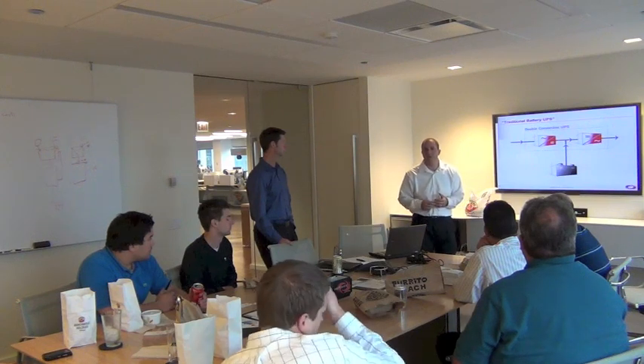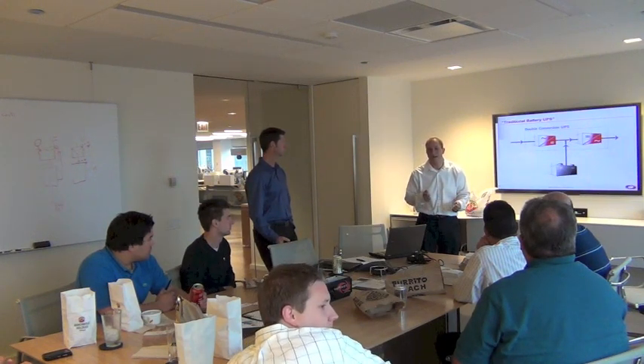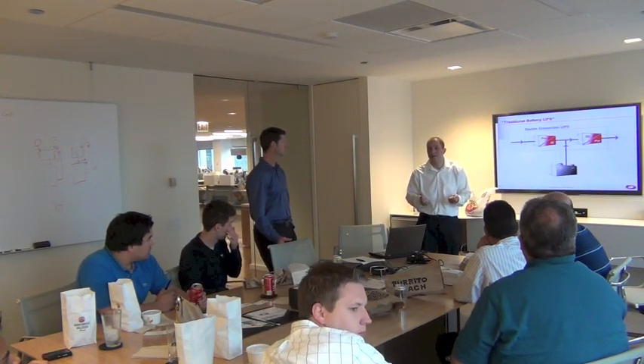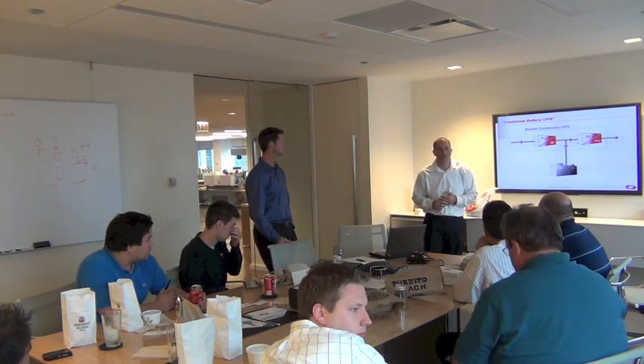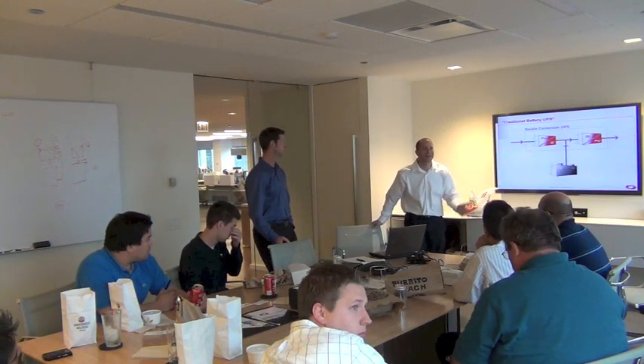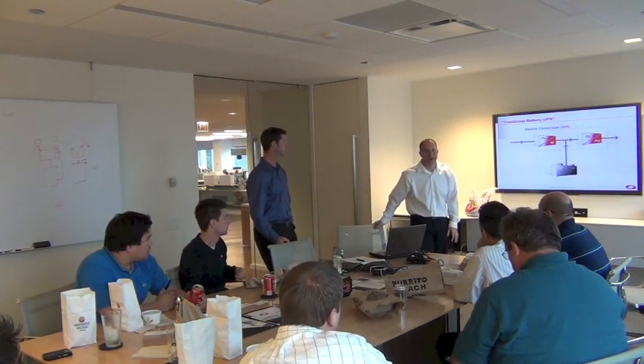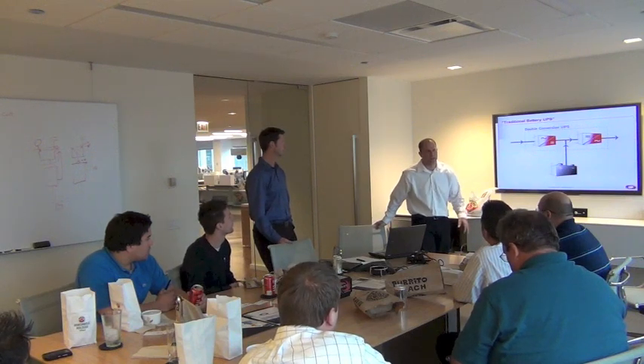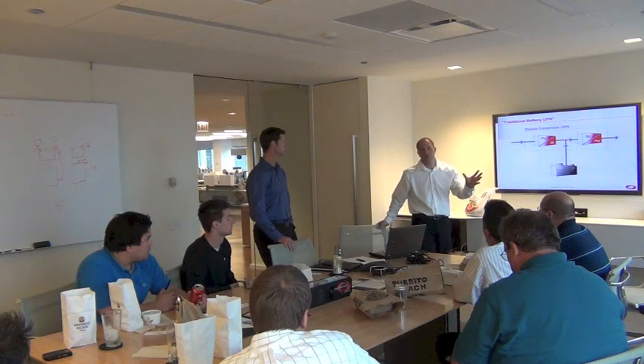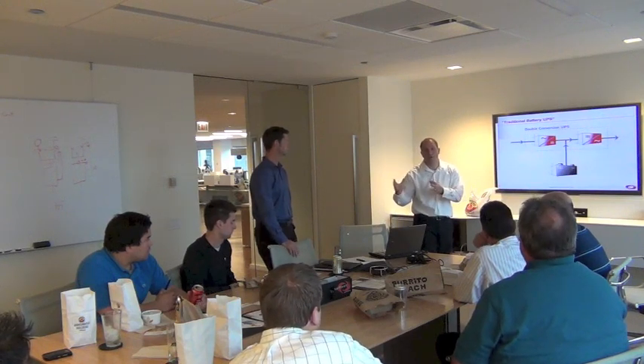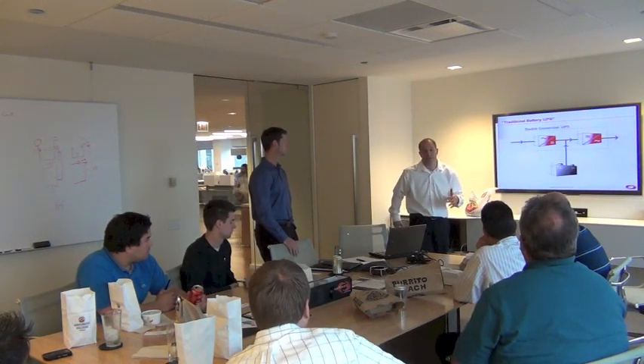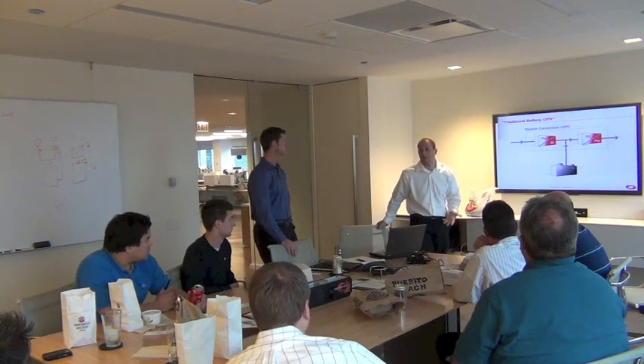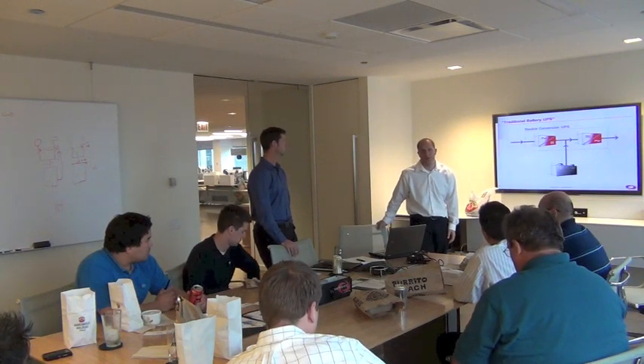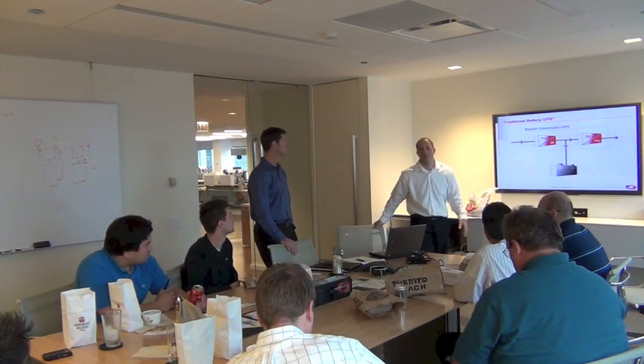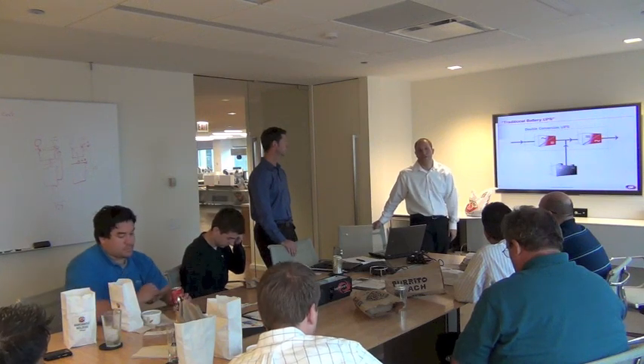We happen to be in a pretty unique situation because we're an online UPS and we're already at 97 to 98% efficiency, so we feel pretty good about being at 98%. There's no real drawback. And I think even the eco mode guys are really between 98 and 99%. Depending on what energy storage they use, for example if you put flywheels off the DC bus, you're going to reduce your efficiency overall by 1% anyway, so you're back in the same boat as we are from an efficiency standpoint, and you're operating offline. There are other concerns with doing that if you transfer back.